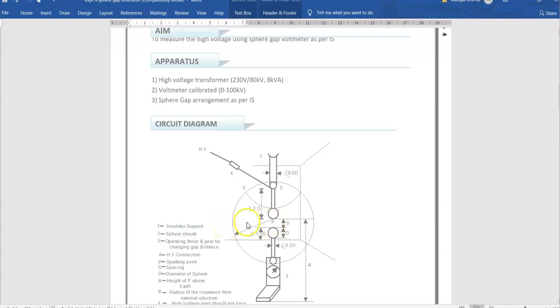Because an unknown voltage is applied, as the gap is reduced, at a certain gap distance that 30 kilovolt, or whatever the unknown voltage is, will cause the breakdown of the air. Now the circuit breaker will trip. We have to isolate the high voltage supply, then discharge the gap, and then go and measure the gap distance.